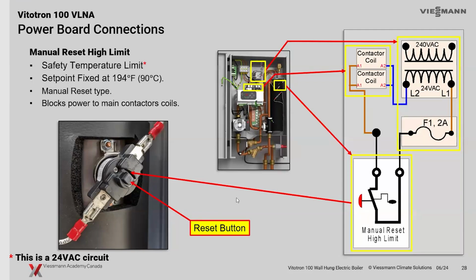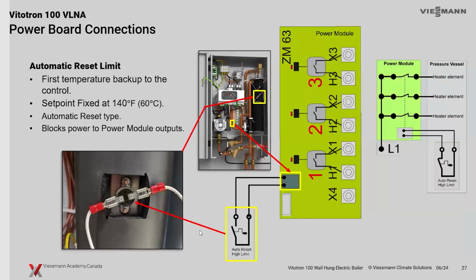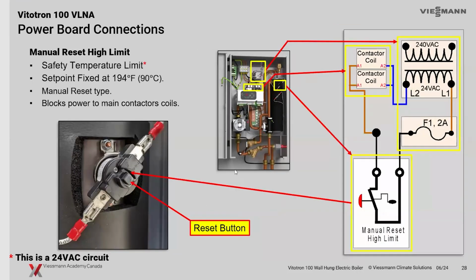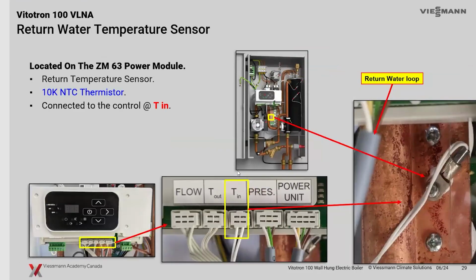So 194, that's going to pop. And this guy here, automatic reset, is going to be opening up at about 140 Fahrenheit. So 140 to 194 is kind of those limits. And we also have a bunch of sensors that are already programmed to this as well. So if you want to do delta T functions and all that kind of fun stuff, this boiler has all of that information for you to read out through a very easy little display.